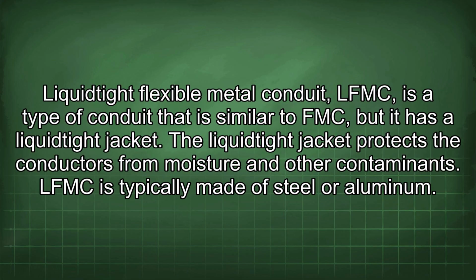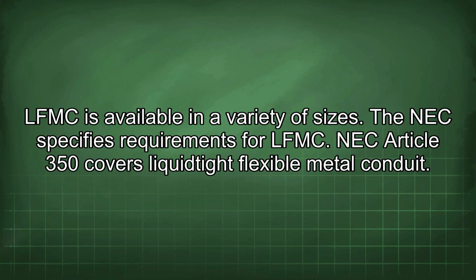Liquid-tight flexible metal conduit, LFMC, is a type of conduit that is similar to FMC, but it has a liquid-tight jacket. The liquid-tight jacket protects the conductors from moisture and other contaminants. LFMC is typically made of steel or aluminum. LFMC is available in a variety of sizes. The NEC specifies requirements for LFMC. NEC Article 350 covers liquid-tight flexible metal conduit.